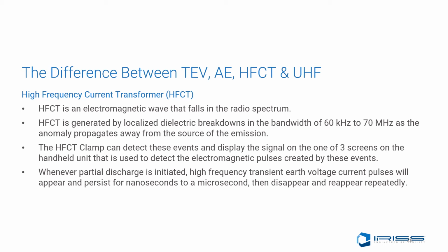The HFCT clamp can detect these events and display the signal on one of three screens on the handheld unit that's used to detect these electromagnetic pulses created by these anomalies. Whenever partial discharge is initiated, high-frequency transient earth voltage current pulses will appear and persist for nanoseconds to microseconds, then disappear and reappear repeatedly.